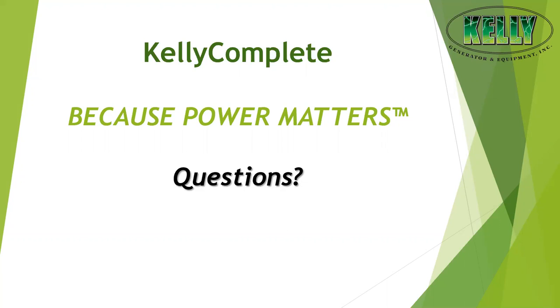Correct. And that's probably better for the Kelly switching people, I'm the software guy, right? But if it's a brand new installation, we install the requisite switchgear necessary for synchronized parallel operation with the grid. If you have a natural gas generator that you've only ever used for backup, meaning when the grid goes down, then you come up, and you can never run synchronized with the grid, we would come in and replace that switch with an automatic synchronized parallel transfer switch. There's a little bit of charge to that, but we don't charge you. It would just reduce your savings. So rather than, in the example I used, going from 10 cents to 9 cents, maybe it's going to go from 10 cents to 9.2 or something like that to compensate for the additional hardware needed. Mark, you may want to comment on that because you're more of an expert in those switching things than I am.